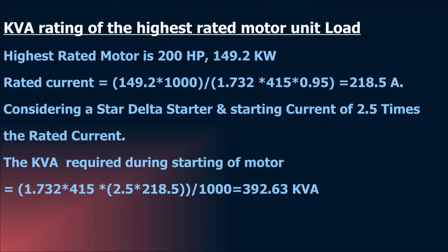In our system, the highest rated motor is 200 HP, and the value in kilowatt is 149.2 kilowatts. The rated current of the motor is arrived as 149.2 into 1000 divided by 1.732 into 415 into 0.95, where 0.95 is the power factor of the system, which will be giving the value of 218.5 ampere.